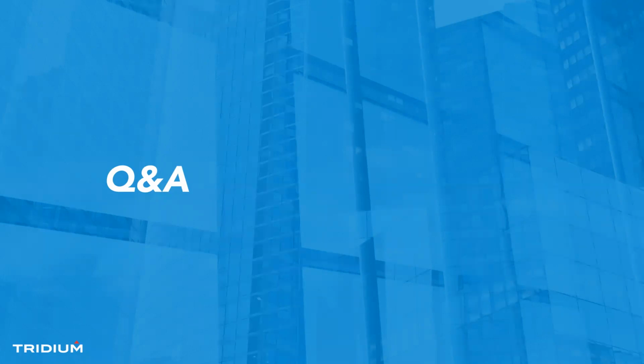Under the covers, it's really just routing Fox messaging. So it says, hey, I got this request, but this request is actually for a downstream station. So it's just going to pass that Fox message down until it gets to the destination station, and then the response will also get passed back up.